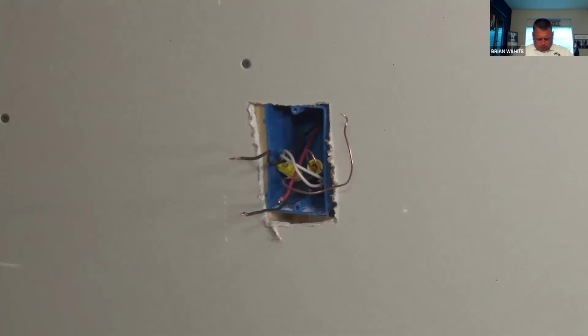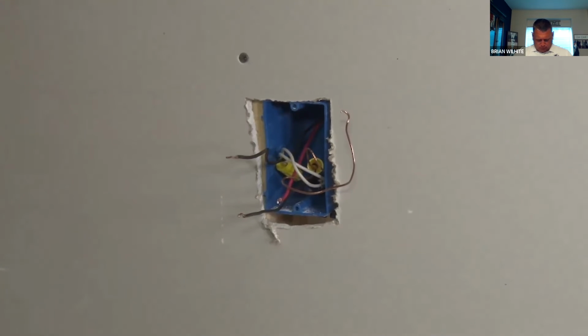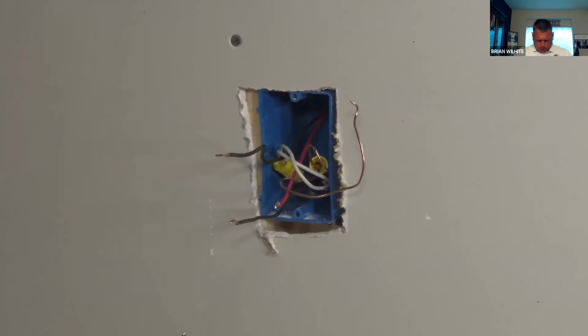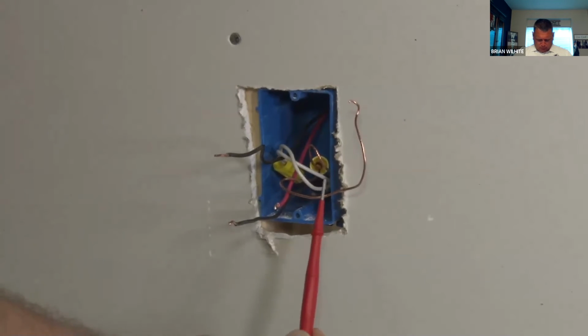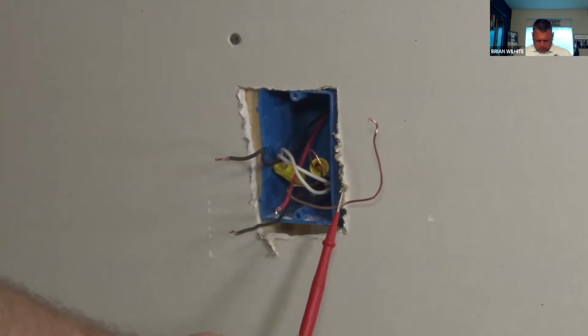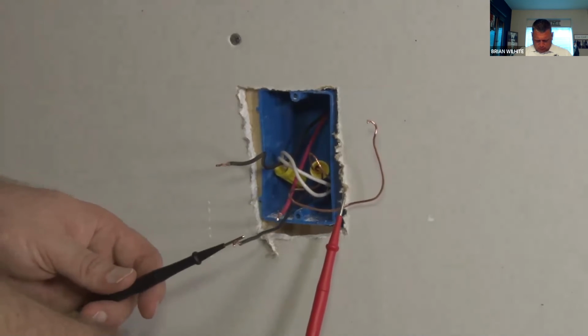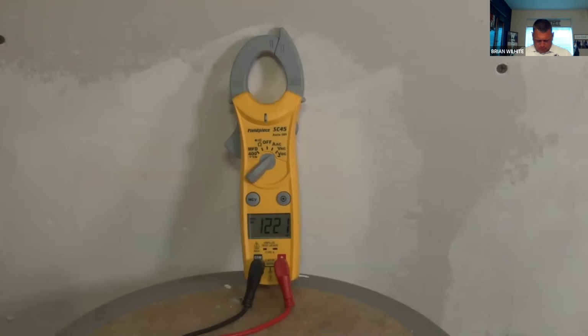The goal of this video is to show how to properly connect a three-way switch circuit by using your meter and determining what the proper connections are. The first step is to take the leads of our meter and determine which wire has power coming from the breaker. In order to do this, we have to turn the power on and safely take one lead and connect it to the grounding wire. And the other lead, we look for voltage in between these wires.